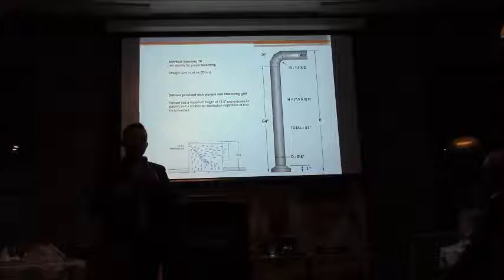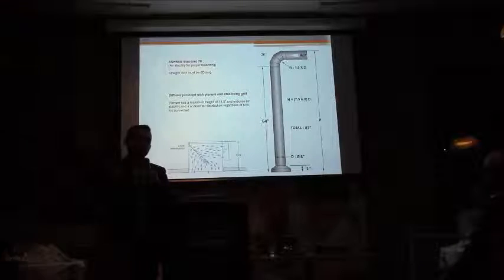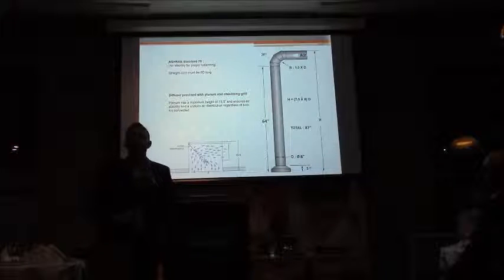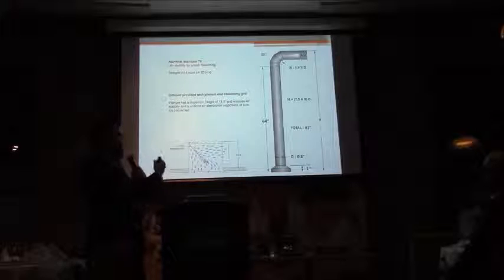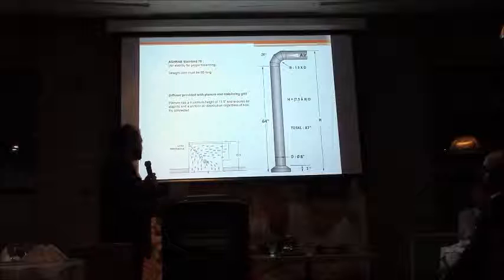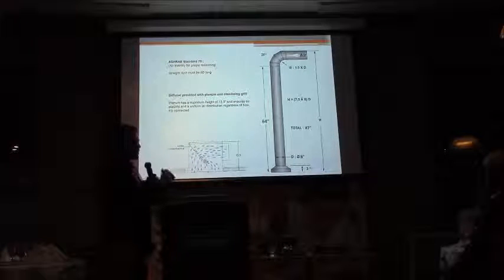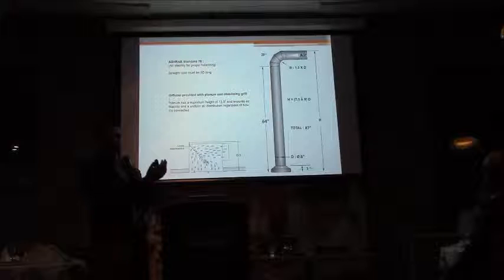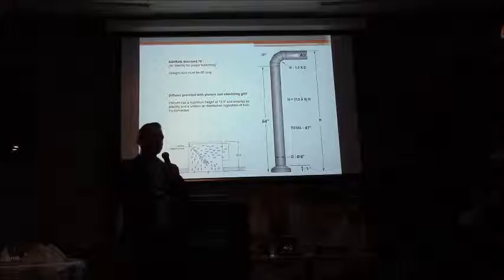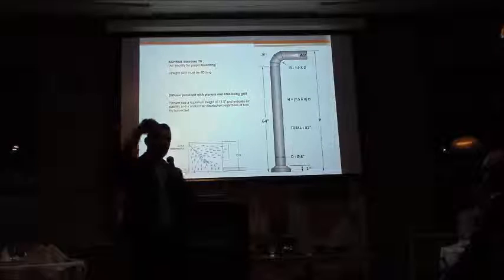And it's not that the Europeans are better than us, it's just that over there the cost of electricity is so much more expensive than it is here, that they're going to save every kilowatt hour that they can. So that's why they use a plenum for every diffuser. It's not just a standard plenum. Ideally, you want to have a stabilizing grill so that the pressure inside the plenum is equal everywhere across the plenum. So instead of shooting straight into your diffuser, you shoot into the plenum, you pressurize it, and there the air comes out evenly across the face of the diffuser.